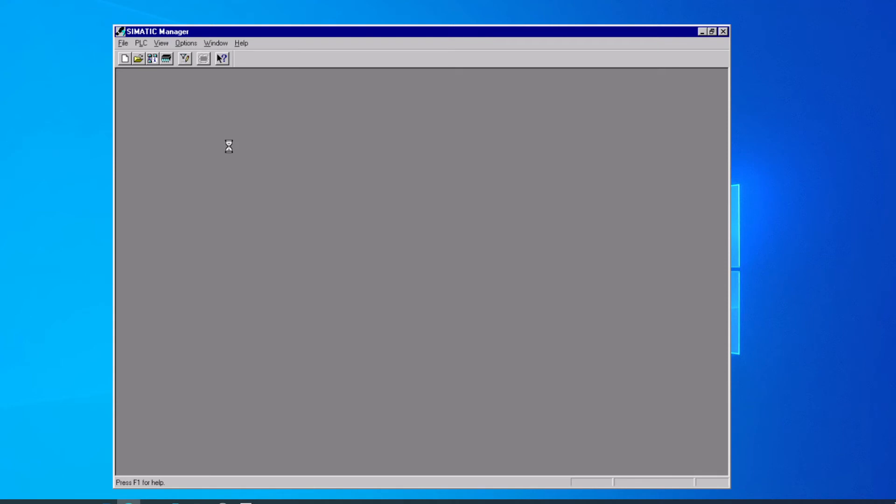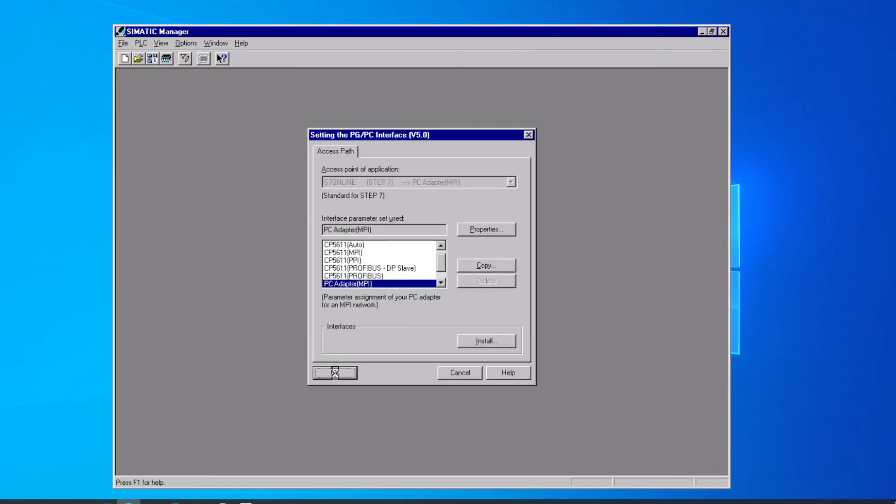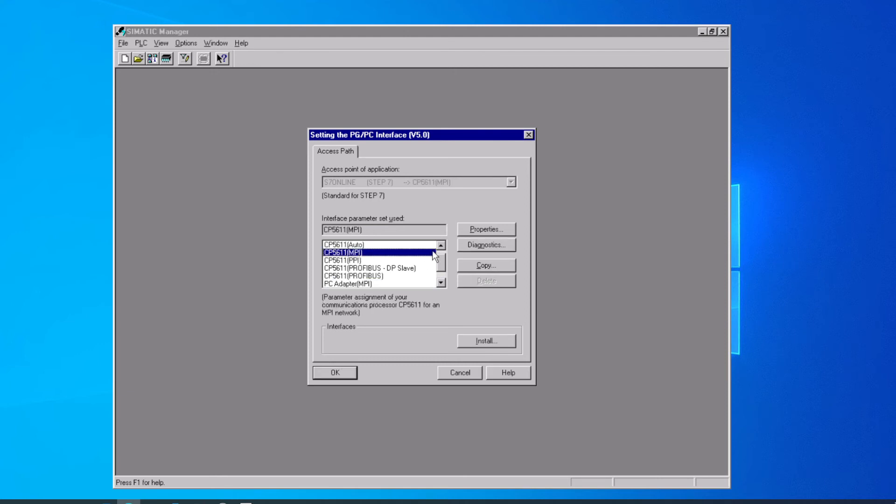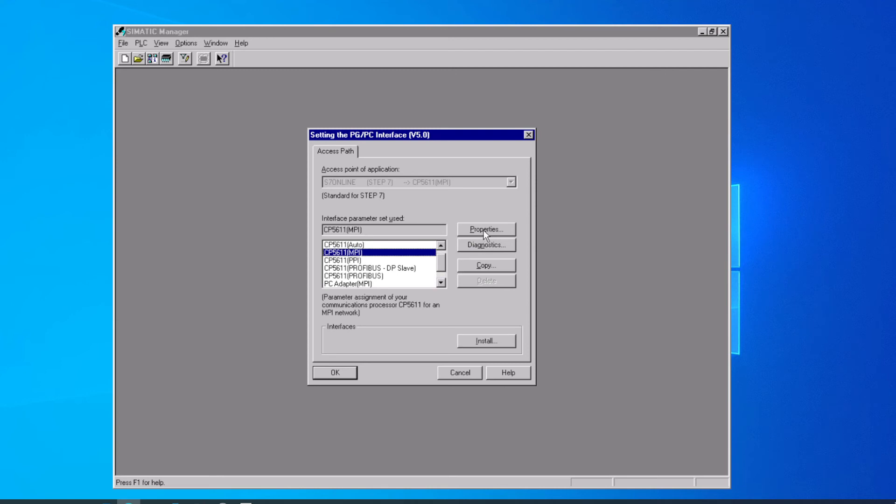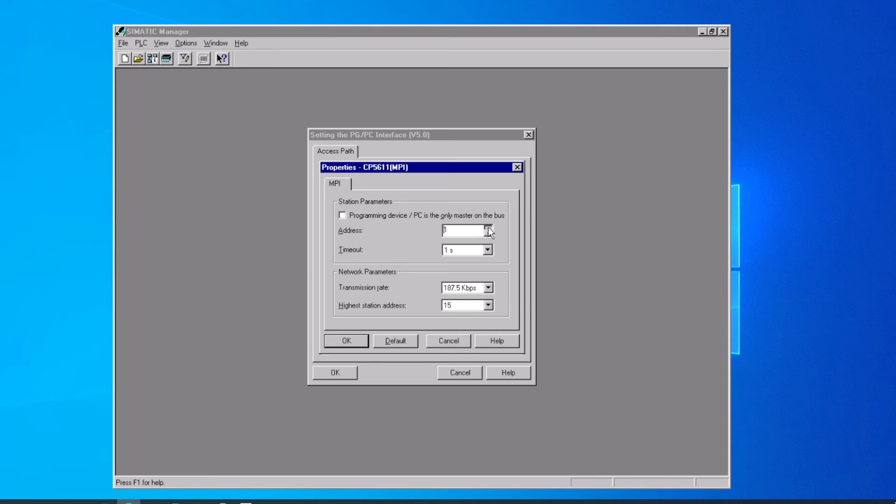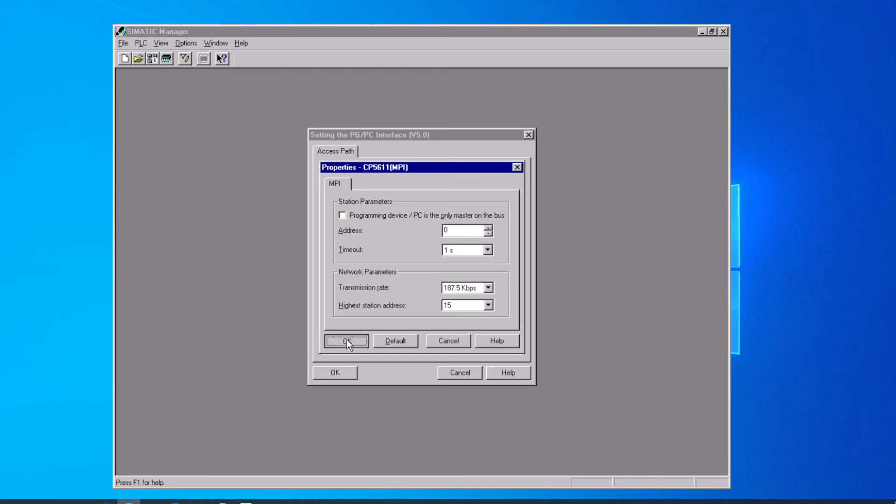If we want to go back and select a different communication path, we go back to the same window again, select the built-in MPI port this time. On the built-in port, we have properties as well. We can set our highest station address down to 15, or up to a higher number if we needed to. We have to make sure that this computer has a unique address on the network.